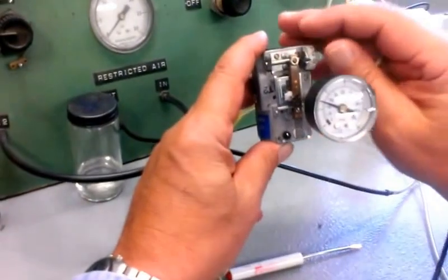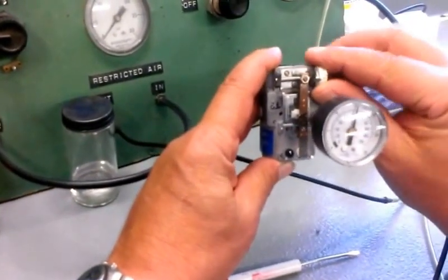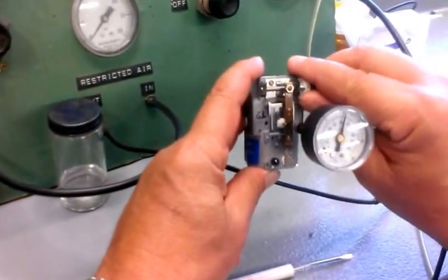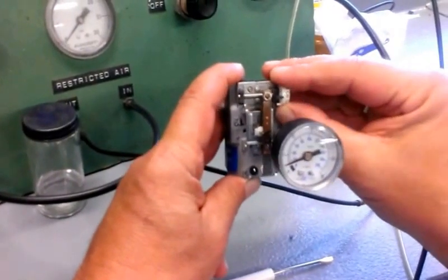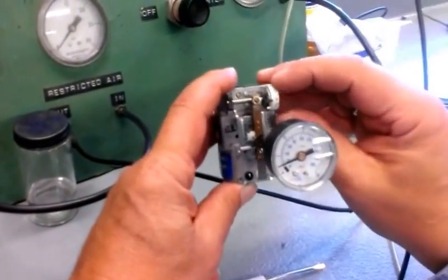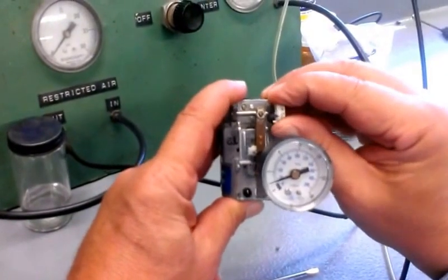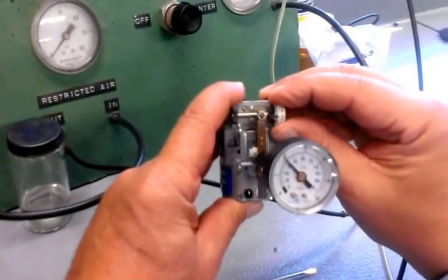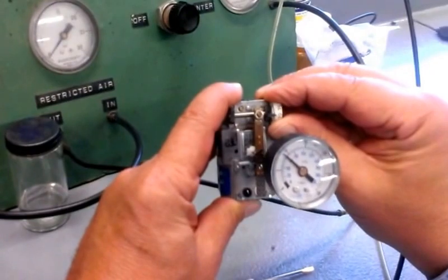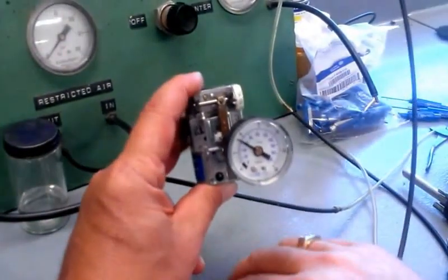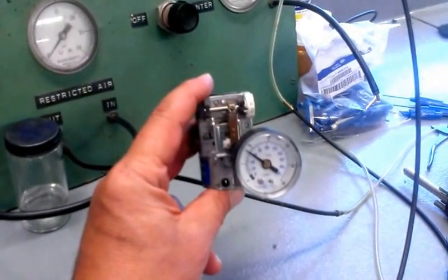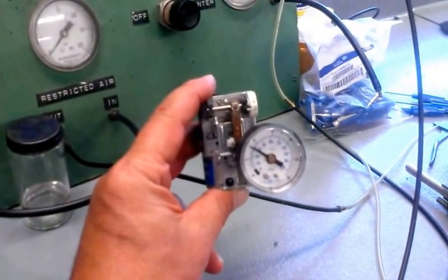So, there's my gauge. Here's my dial. I get full pressure. It bleeds fully, so I know I don't have a bleed or a build-up pressure. So, I have something to work with here. I'll turn it to 72 degrees, and I want to be between 8 and 9 pounds, which is where I am. I'm just about 9 pounds.